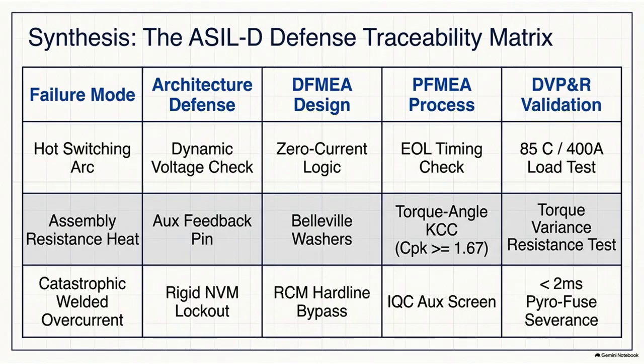And the validation engineers are the ones controlling the parameters of the game, intentionally acting maliciously. They actively try to trick the software. They intentionally fake the pre-charge failures we discussed. They tell the supercomputer to pretend the voltage difference across the contactor is dangerously high, creating a mathematical delta V greater than 5%, perfectly simulating a burned-out pre-charge resistor. They are actively trying to trick the BMS into making a fatal error, trying to get it to close the main switch and cause a massive simulated weld.